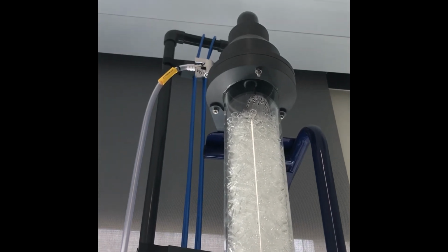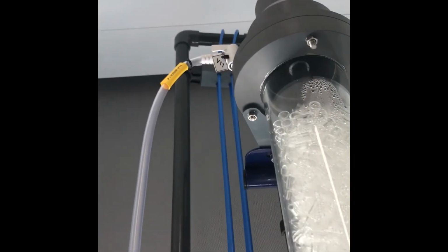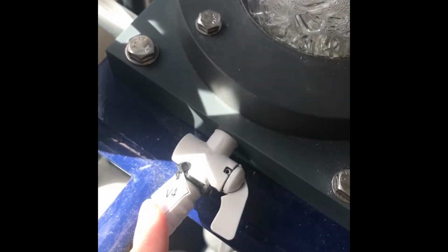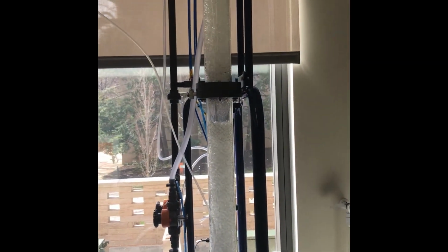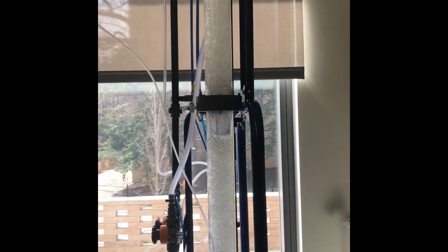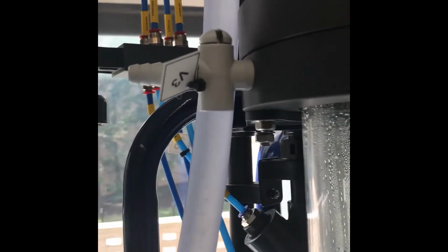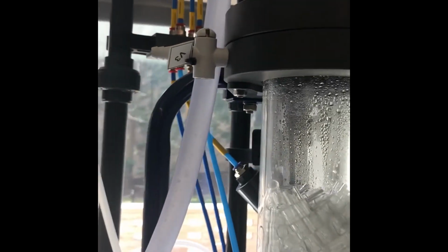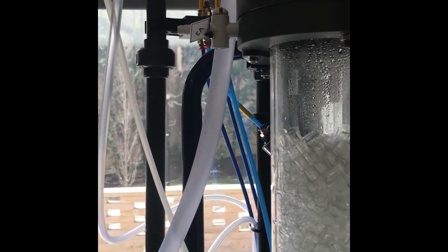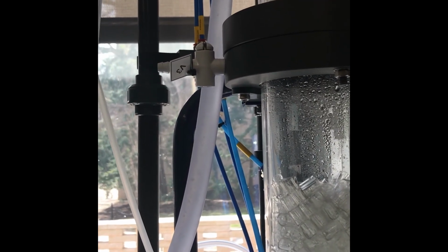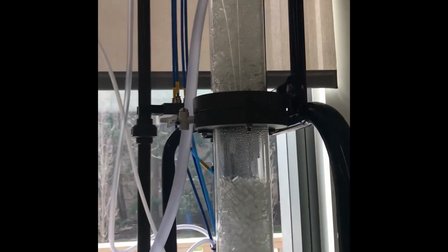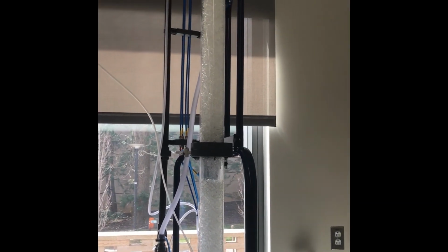From the top to the bottom of our column, we have three valves labeled V11, V3, and V4. These valves are used for reading the differential pressure along our column. V3 is kept closed, as you can see, but if this is open to the atmosphere, we read our pressure differently. But we want to keep that closed so that we can read gauge pressure through our software in order to use those values properly rather than having to account for atmospheric pressure.